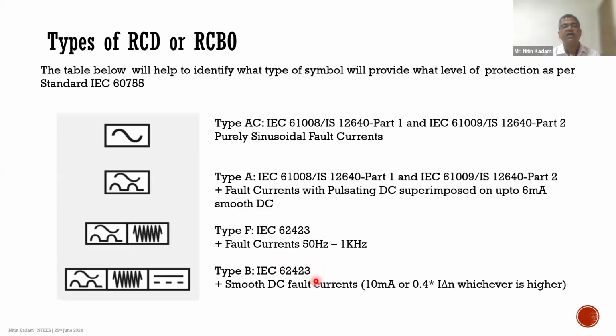Let us see now what are the types of RCDs or the RCBOs that are available. If you have an RCD which can only detect AC leakage current, it is called a type AC RCD. In case of type A RCD, it can detect both the AC current as well as the pulsating DC current. In case of type F, it can detect the AC current, pulsating DC current, and fault currents in the frequency of 50 Hz to 1 kHz. Type B can detect the AC current, pulsating DC current, high frequency currents, as well as the smooth DC current or the filtered DC. These are the type B devices which generally should be used in the application for elevators.